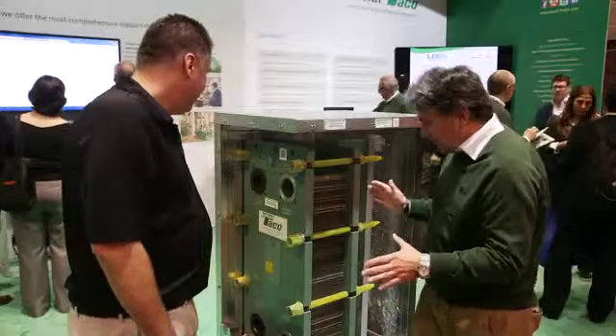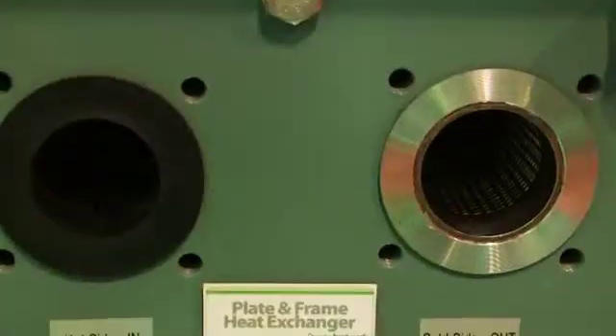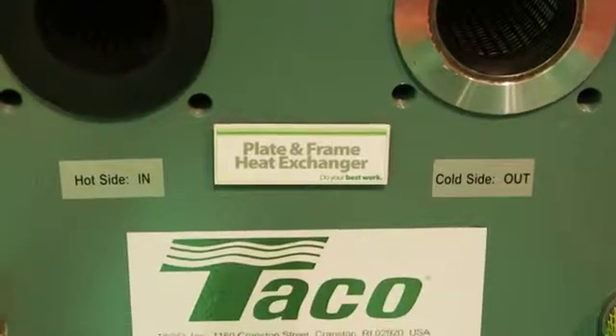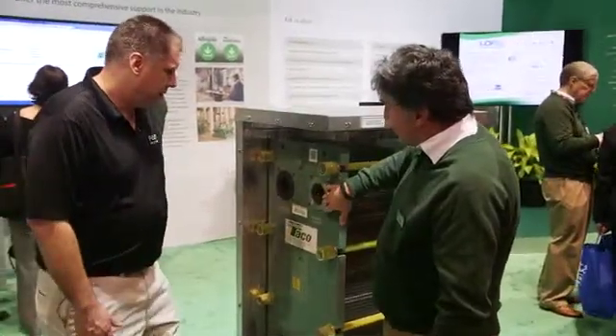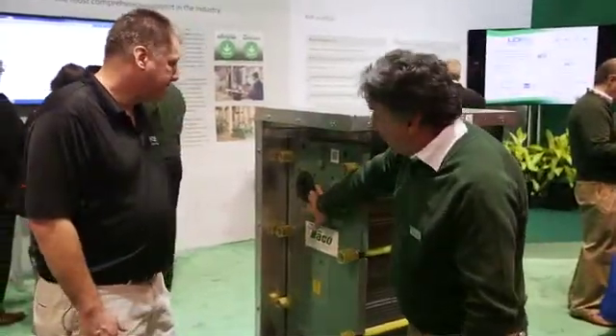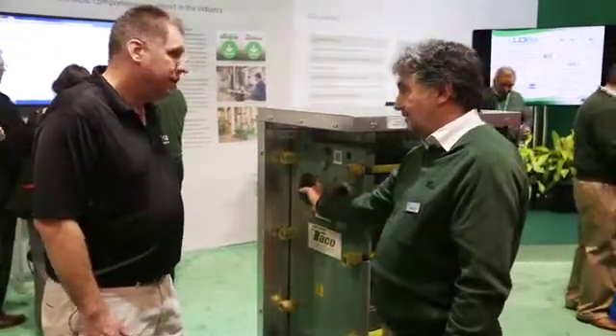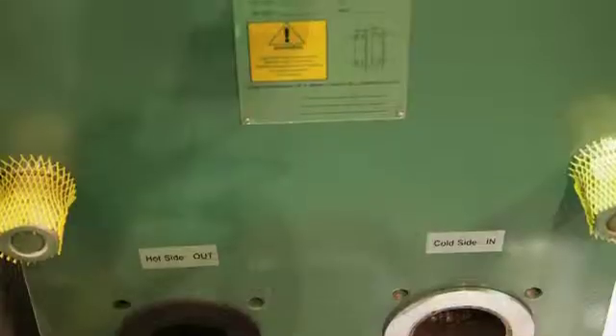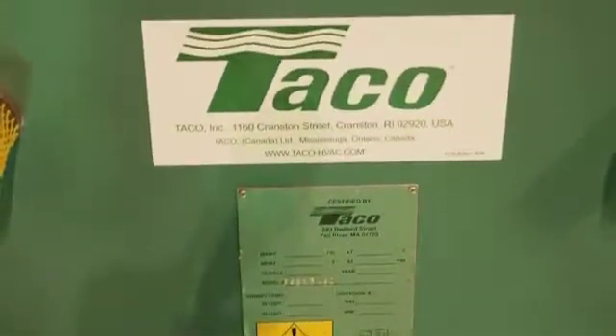Pretty accurate. Yeah. And the other thing is we can put different liners in the ports. So we do not like to just put carbon steel. Some people will just bolt against the frame. What we want to do is we give you an option of stainless or an elastomer. So if we're using nitrile inside, we're using a nitrile elastomer here. I see. And it's all studded ports, and on very small things we're doing NPT, 2-inch and 1-inch. But this will be like a flange connection then? That would be a flange connection. Gotcha. And that would be your actual seal, right? I see. Okay.